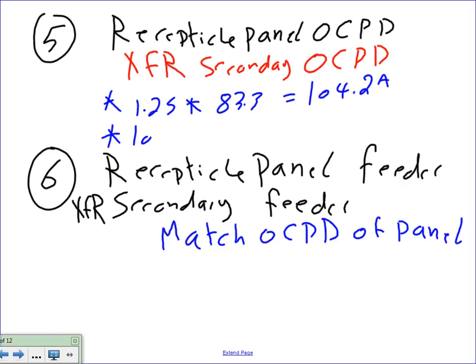Then you go 104.2. Take this baby to, now this time a different table, 240.6. And if you take this one, what's the next standard? Go to the next standard. What's the next standard overcurrent protection device? 110. 110. So this overcurrent protection device will be 110 amp.